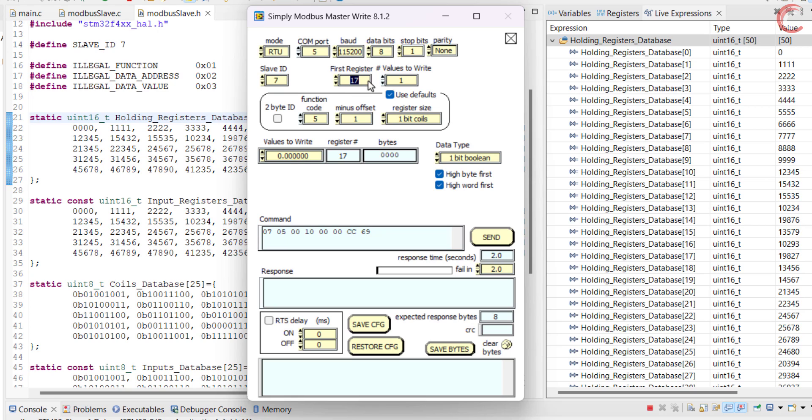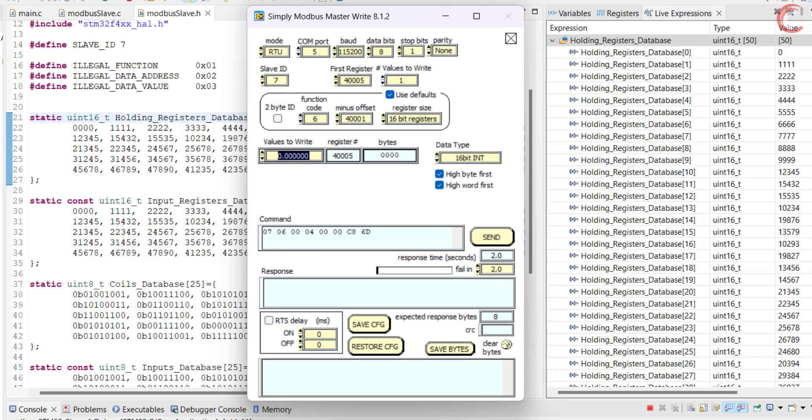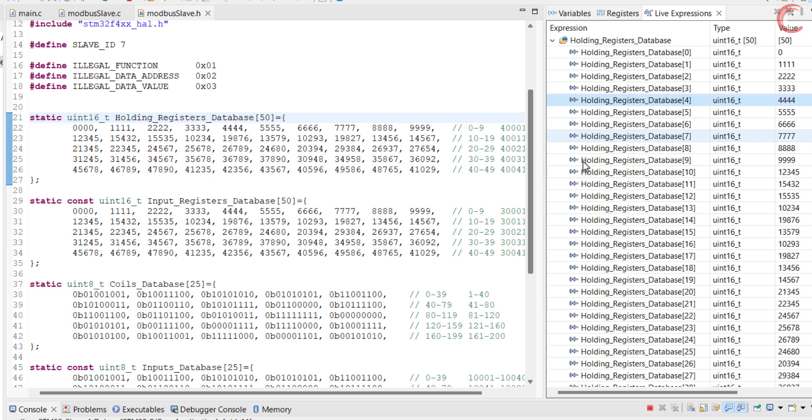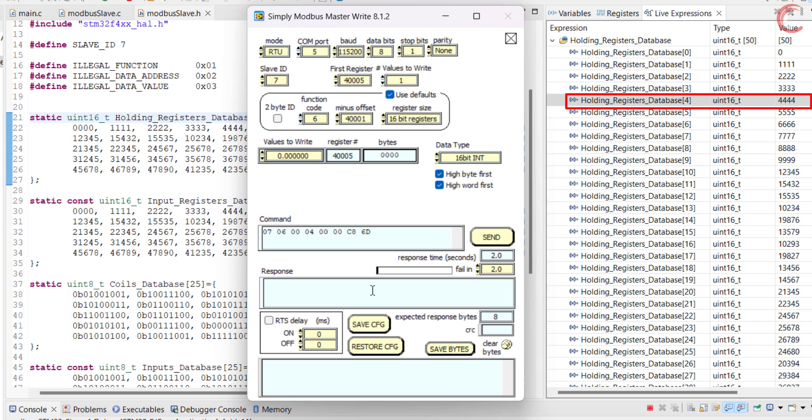Let's start by testing the single register. Let's say the master wants to write the register at the address 40005. Since it is writing only one register, the function code is set to 6. Here you can set the value for the register. The current value at 400005 is 4444, and the master wants to update it to 12345.